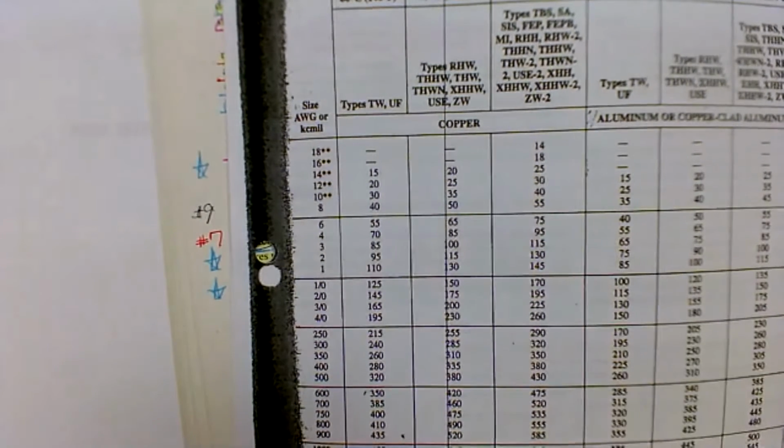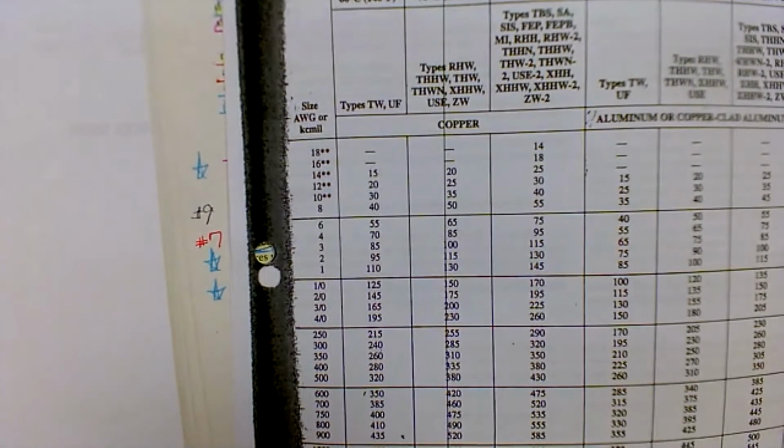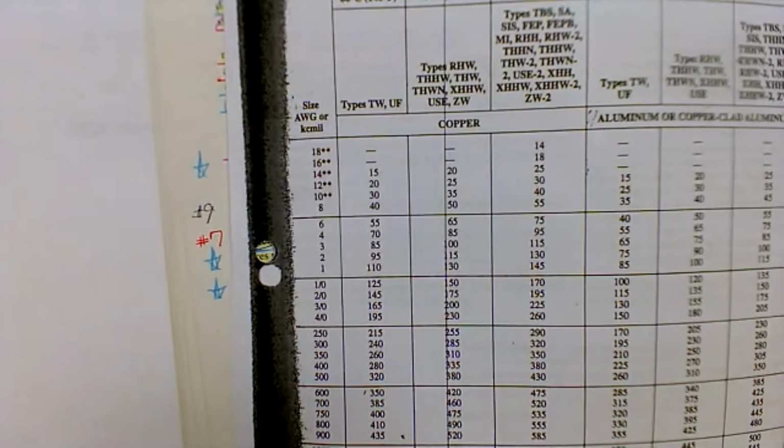Yep. But a lot of people never look at this stuff, and it bites them in the rear. Anybody that's worked in a plant or on a farm for very long has had to pull wire out of conduit that was melted. Have you ever seen any melted, Jamie, that you pulled out? Oh, yeah. Maybe more than one time? Oh, yeah. We ran into that Monday, as a matter of fact. So you pulled some wire out and it was melted.